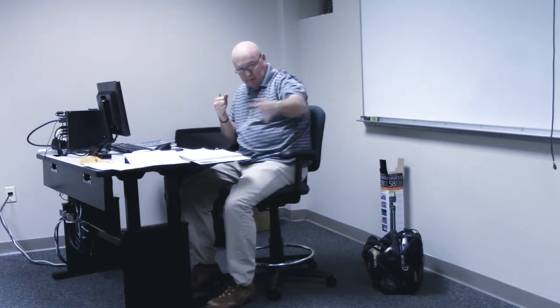Okay, that means in a Class 1 location, we don't want the plug to be where it could come loose and be sparking in those areas. So we've got a different type of plug, a more expensive plug, a locking plug, the ones that are formed, not like the normal plug. You actually have a different plug and a connector, don't you? They actually match and go together. Okay, so we've got to have that. That's a Class 1 location.